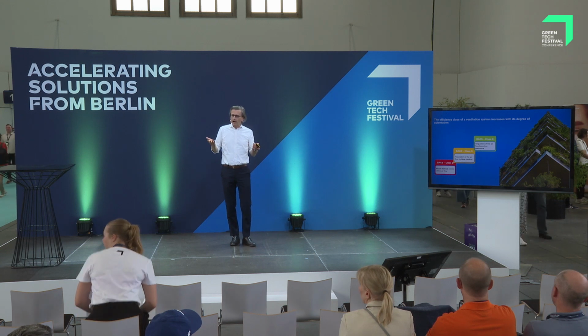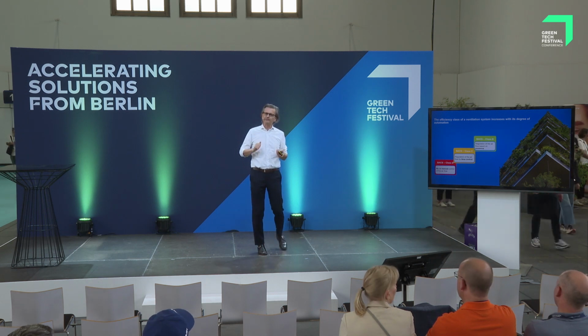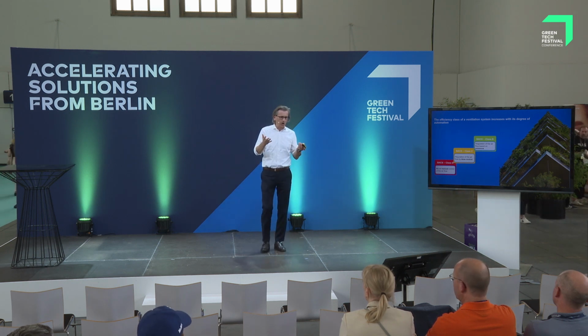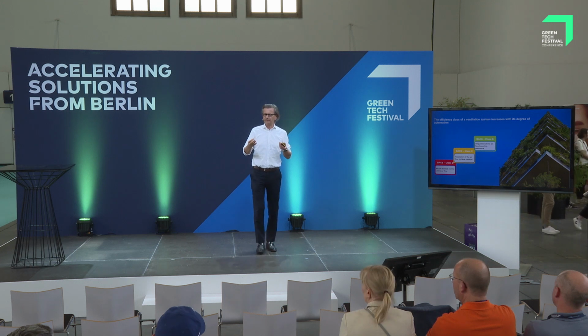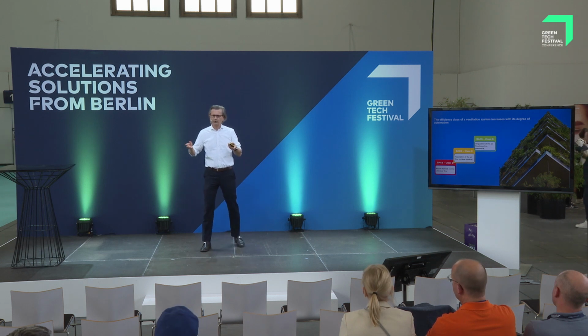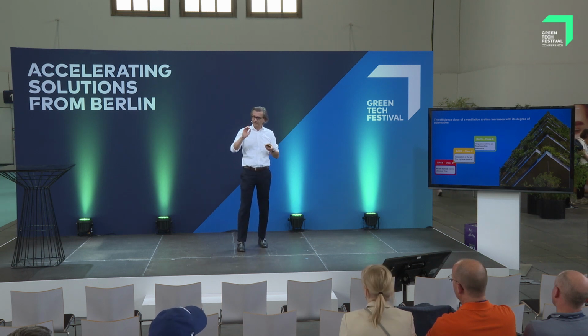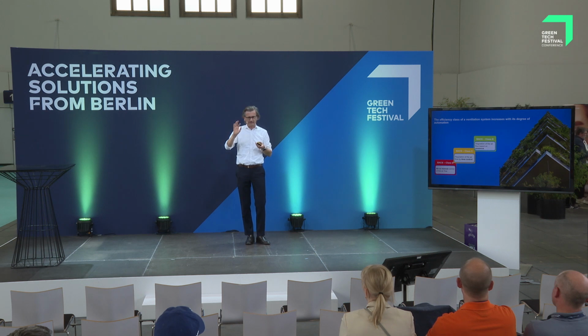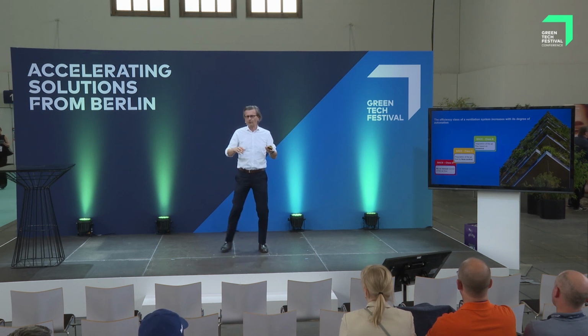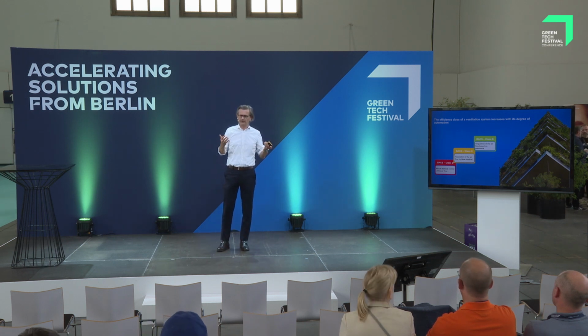The class which is now required in buildings with a bigger amount of technology is this Class B. Class B means in the air conditioning area, the system is only on if there's somebody in the building, if there's somebody in the conference room, if there's somebody in the kitchen, wherever. So the system recognizes there is somebody there, and then the system starts running. That's pretty smart, and it's pretty effective. But whether there is one person in the conference room, or 15 or 50, such a system does not differentiate between the amount of people.